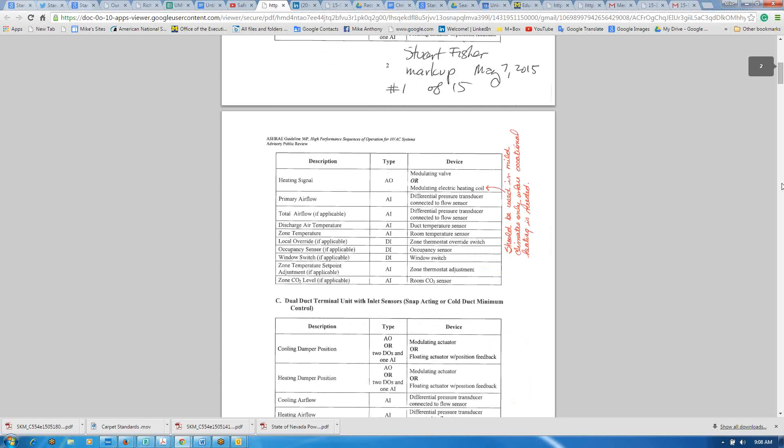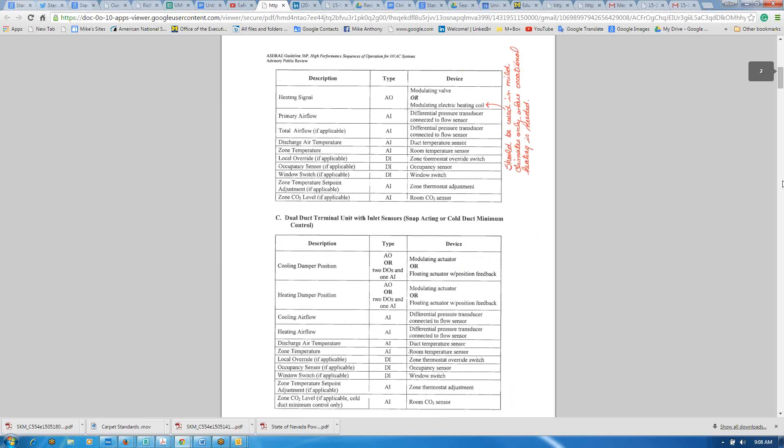I have a basic concern with the reheat system in general, where we're cooling the air stream down and then turning around and reheating it. So that's what I had for page 2. On page 3 under that same thing, heating signal, modulating electric valve. I realized that in milder climates you can use them where they're only occasionally used. But here in Michigan, I know of one application when I worked for Chrysler where they didn't want to install a separate boiler system for reheat. The main heating for the building was done with gas-fired rooftop units. They didn't want to install a separate boiler for hydronic heating coils, so they installed electric. And it was just an energy nightmare and a maintenance nightmare.